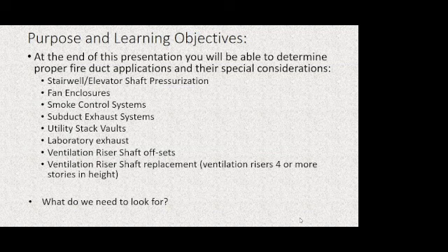Ventilation riser offsets: the floor plate changes, or simply the architect desires some freedom of design. And so the riser is over here on one floor plate, and on the next floor plate above or below, it shifts on the plan. We have to get horizontally from one to the other, and we have to often maintain our fire resistance rating of that offset. We'll talk about when you do, when you don't, and what the difference is.